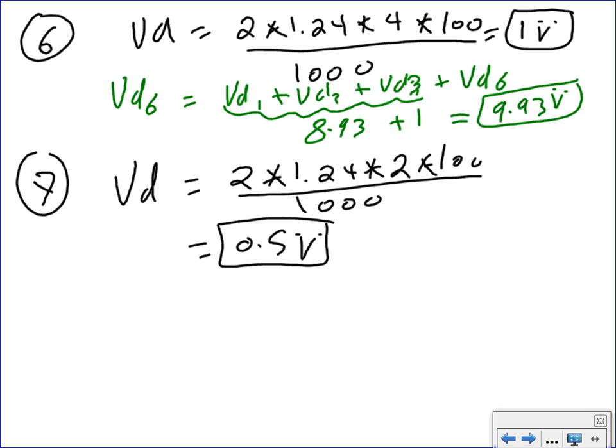If you do the same math that we did, that will give me 9.93 divided by 120 equals the voltage drop. What did we come up with here? 8.3, 8.3%. The last section, guys. Did we do anything wrong here? Anybody? We add them up? Yes, sir. The one that you're adding on to 8.93, was that the first 3 from number 4? That was from number 6. Oh, okay. Number 4 is a different branch. I got it. It didn't go through it.